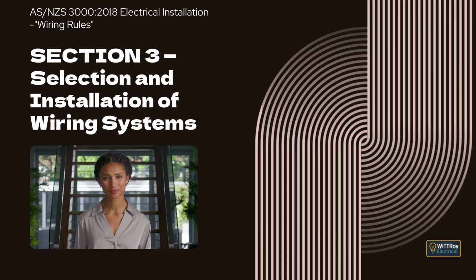Clause 3.9.8.1, General. This clause explains that wiring systems must be arranged to avoid detrimental effects between different electrical installations, different voltage levels, safety services and non-electrical services. Clause 3.9.8.2, Different electrical installations. This clause states that conductors from different electrical installations must not share the same enclosure unless specific conditions apply, and clarifies what is not considered an enclosure.